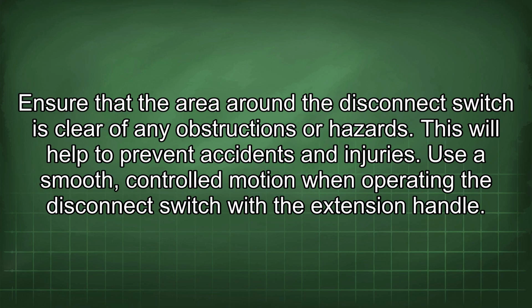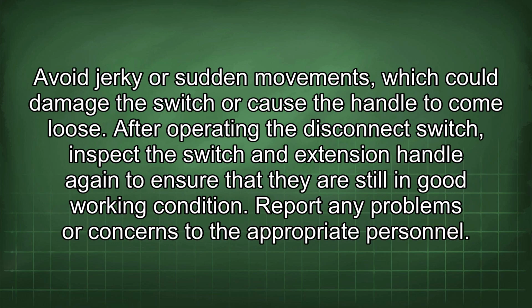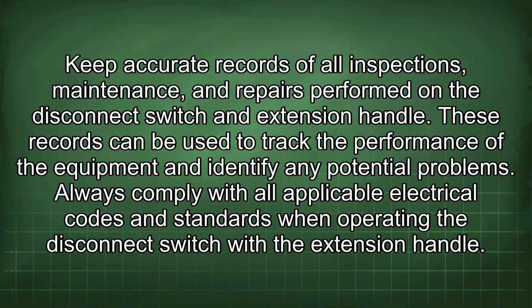Ensure that the area around the disconnect switch is clear of any obstructions or hazards. This will help to prevent accidents and injuries. Use a smooth, controlled motion when operating the disconnect switch with the extension handle. Avoid jerky or sudden movements, which could damage the switch or cause the handle to come loose. After operating the disconnect switch, inspect the switch and extension handle again to ensure that they are still in good working condition. Report any problems or concerns to the appropriate personnel. Keep accurate records of all inspections, maintenance, and repairs performed on the disconnect switch and extension handle. These records can be used to track the performance of the equipment and identify any potential problems. Always comply with all applicable electrical codes and standards when operating the disconnect switch with the extension handle.